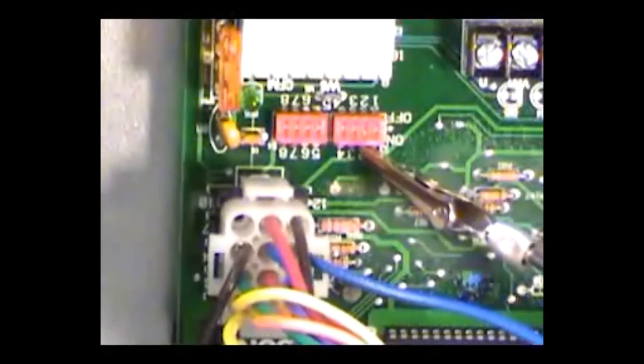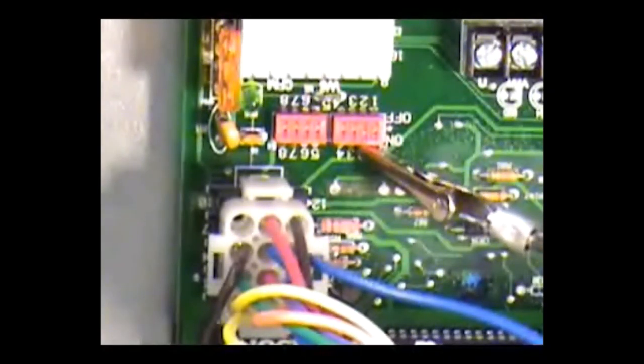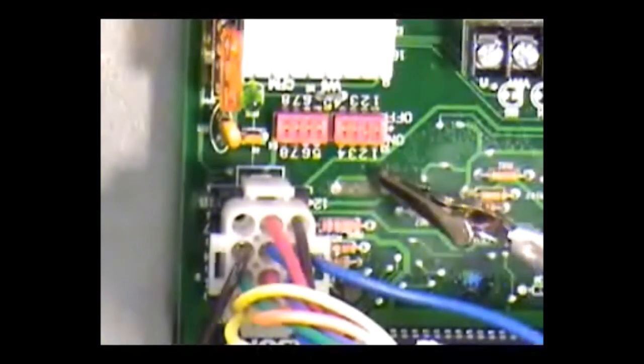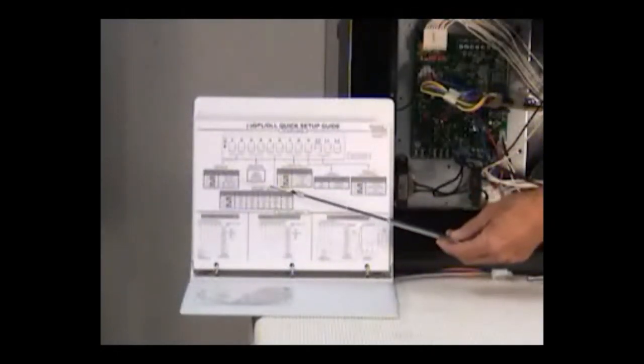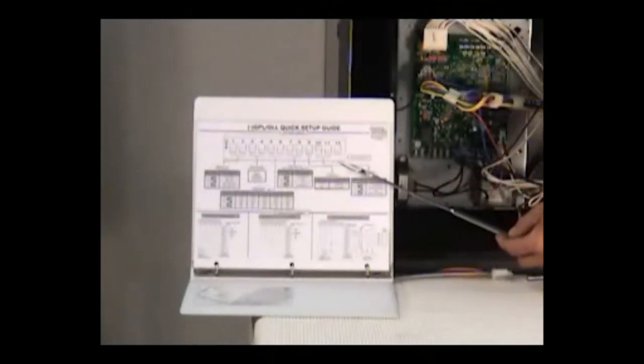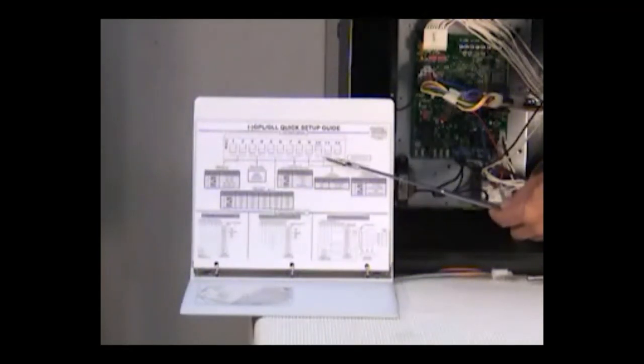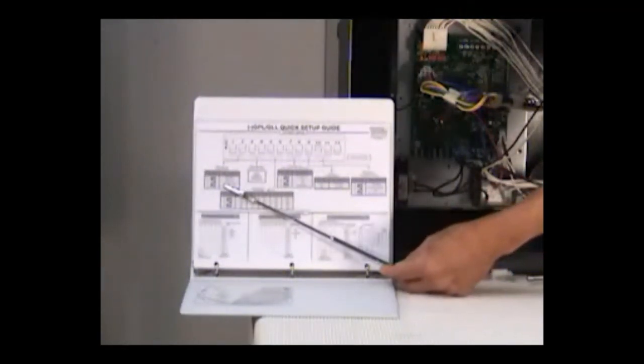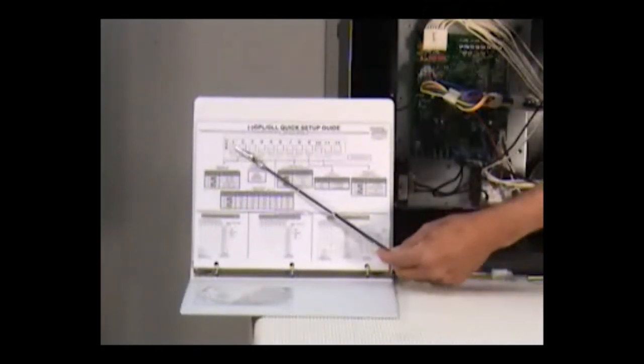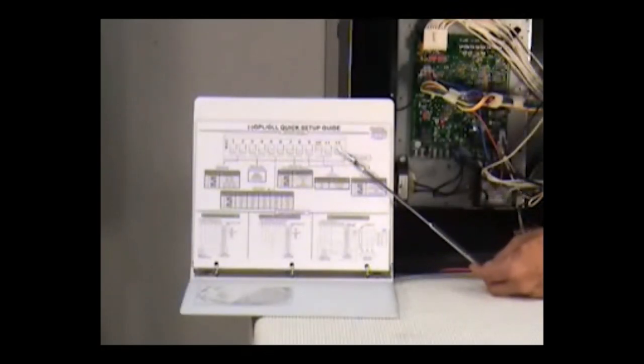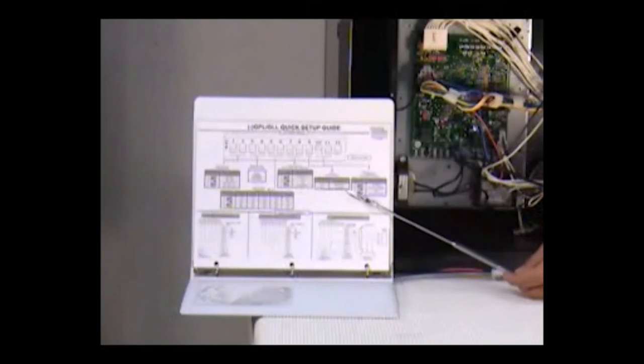The fourth pair will actually be an overall determination as to the speed. It can be adjusted to where we will add to the speed that we currently have set, or subtract or take away from the speed. So we could either have more airflow or less airflow by a minor adjustment through the last or fourth pair. Okay, not all manufacturers will do it the same, nor do they have the same setup as far as the arrangement or the array of dip switches. As you can see here on this one, through a manufacturer's setup, they are showing a different setup as far as the 1 and 2, 3 and 4, and so on switches, or dip switch settings that they have in this particular one right here.